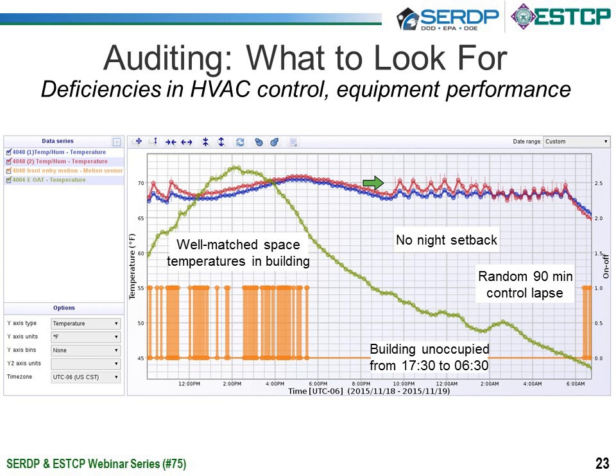In fact, up to 25% of the building savings can be achieved just through night setback. So in this case, you can see this is data from November, so this is the heating season. This is the heaters kicking on here. And at nighttime, you can see the system's clearly heating and maintaining around a 68-degree temperature set point. It's not setting the temperature back to a 60 or 62, which is achievable. So there's clearly no night setback here.